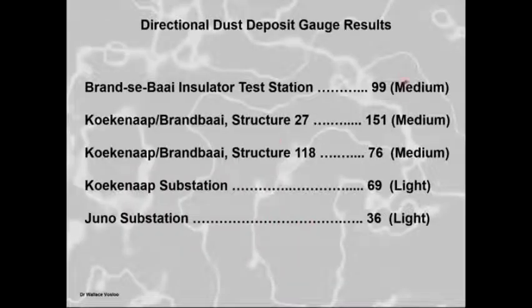Now, in the area, we built a test station quite close to the coast at the line, an online test station. Actually, that test station was used to write the CIGRE 555 guide on establishing test stations, along with some of my other test stations. So if you want to build pollution test stations, you can have a look at the CIGRE guide. But coming back to this, we built a test station and put up in it each and every possible insulator combination we could, to prove to this group of people that are deciding that we need to re-insulate with the blue one, that it's not necessary, the blue one's not going to work. There's another problem. But anyhow, at this test station, we measured a pollution index of 99.